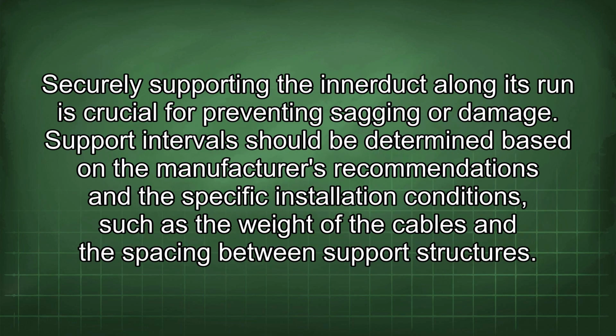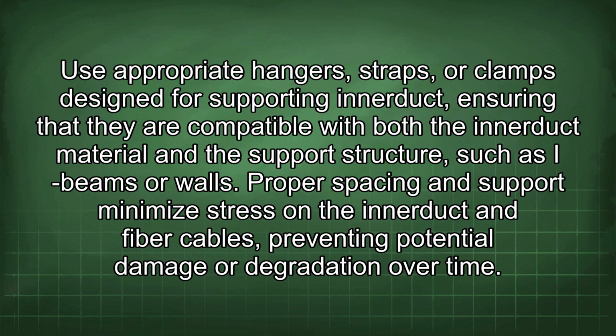Securely supporting the Innerduct along its run is crucial for preventing sagging or damage. Support interval should be determined based on the manufacturer's recommendations and the specific installation conditions, such as the weight of the cables and the spacing between support structures. Use appropriate hangers, straps, or clamps designed for supporting Innerduct, ensuring that they are compatible with both the Innerduct material and the support structure, such as I-beams or walls. Proper spacing and support minimize stress on the Innerduct and fiber cables, preventing potential damage or degradation over time.